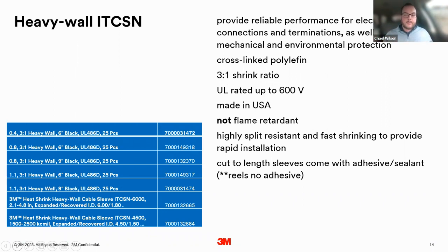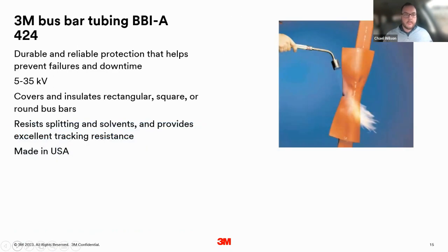You can go ahead. We also have bus bar tubing for heat shrink. Bus bar tubing is specifically designed for bus bar. Probably could have figured that one out. And the reason why is because standard heat shrink tubing is cylindrical, and it wouldn't really fit around bus bar. So this is designed to shrink around that square bus bar, and it's a little bit larger to fit those bus bars for you.